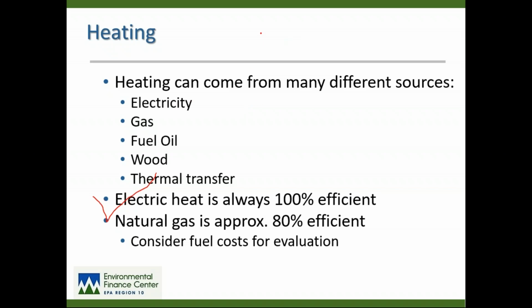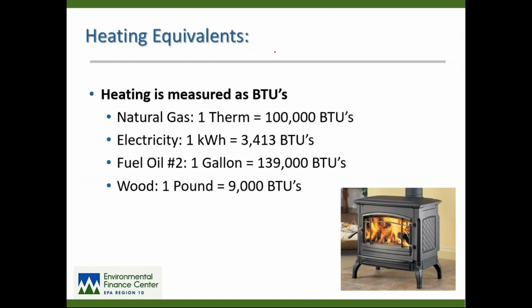And again, that's industry-wide. Consider all of your different fuel costs when you're comparing heating. These are some of the fuels that are available. Again, heating is measured in British thermal units, and you might see these terms on your gas bill or your energy bill. 1 therm is equal to 100,000 BTUs. 1 kilowatt hour is equal to a little bit more than 3,400 BTUs. 1 gallon of fuel oil will provide 139,000 BTUs, and a pound of wood is about 9,000 BTUs. So just some terms and how they compare, and terms that you might see on an energy bill.